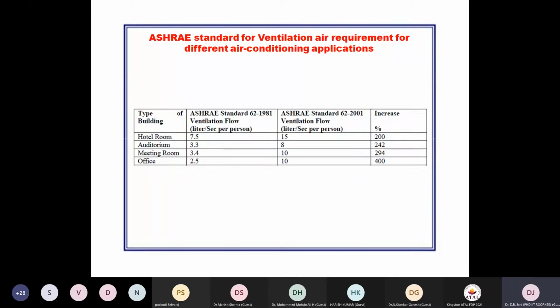The standard given out by ASHRAE in 1981 was ameliorated in 2001 with a percentage increase in the previously determined ventilation airflow, which is typically measured in liters per second per person. However many persons are in the closed occupancy, a different liters-per-second airflow is required as ventilation airflow. In our household applications these days, we typically use a split air conditioner. One limitation of split air conditioners is that they do not provide any fresh air. You have to open the door partially during door-opening hours, or open your windows slightly, 2 to 5%, to exchange air. This ventilation airflow is necessary to provide fresh oxygen.